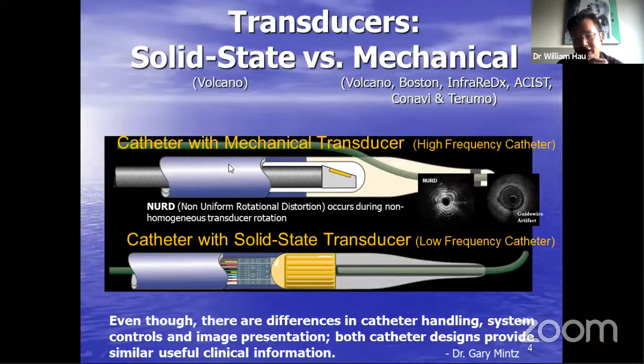And the other type of IVUS catheter design is the solid state. It has 64 transducers located at the distal end of the catheter, and you automatically switch one by one to capture the IVUS image. This is a much more user-friendly system, but the image resolution is not as good as the mechanical type of IVUS catheter, because the frequency they're using is only 20 megahertz.